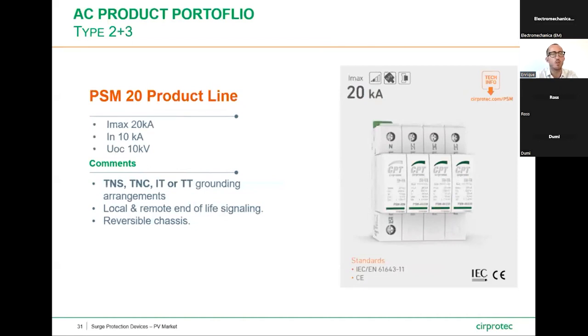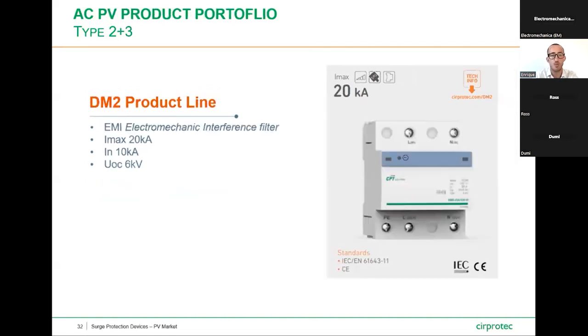Then we have our type 2 plus 3 product range, our PSM 20 with an Imax of 20 kA, with an In of 10 kA, and declaring a UOC parameter for the type 3 test of 10 kilovolts. Those are suitable for TNS, TNC, IT, and TT systems. We also have solutions available with local and remote end of life signaling. And the same as before, those have reversible cartridges. And the last one is also a type 2 plus 3 SPD, sorry, with an EMI filter. What does it mean? An electromagnetic interference filter for a specific application when it is required. It's declaring an Imax of 20 kA and an In of 10 kA. At the end, for the type 3 test requirements, it's declaring a UOC of 6 kilovolts.